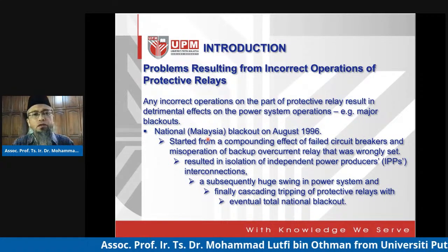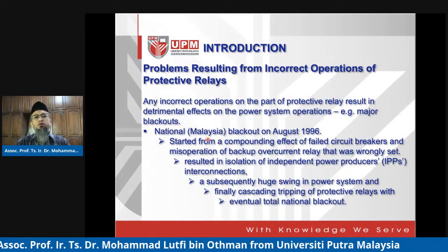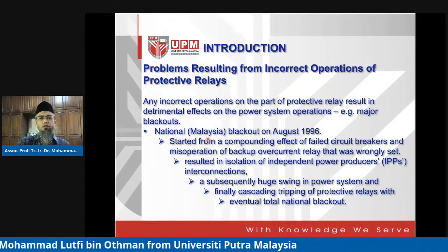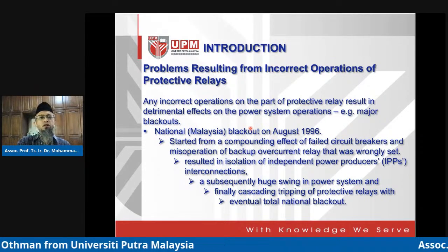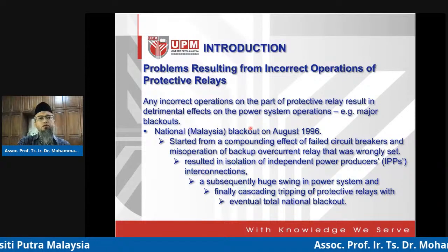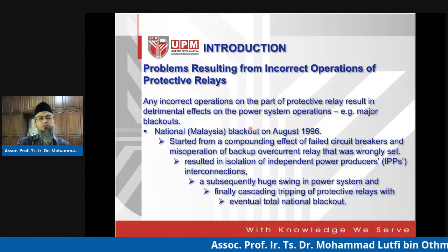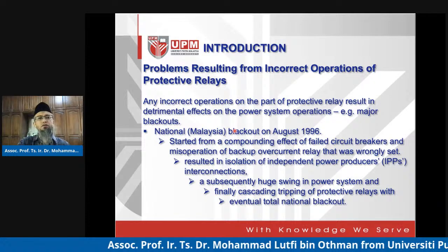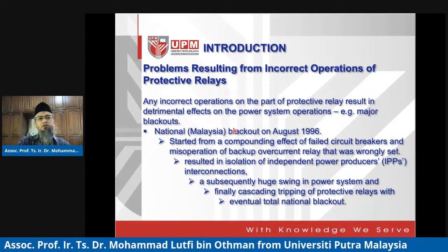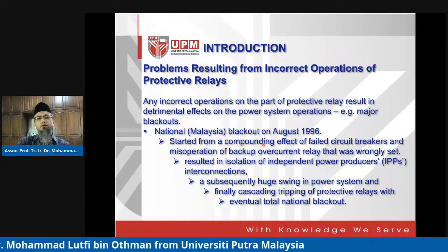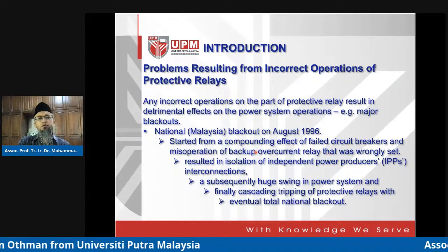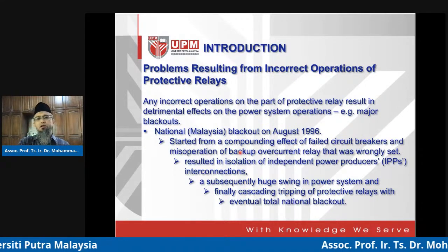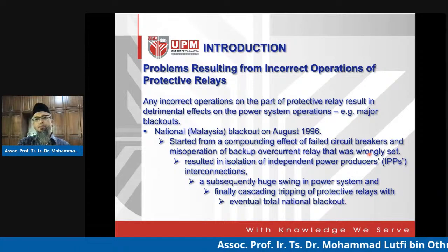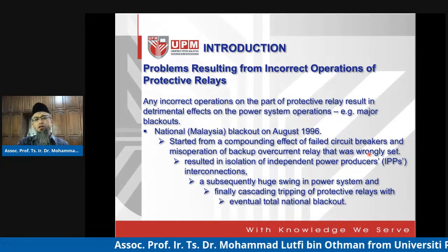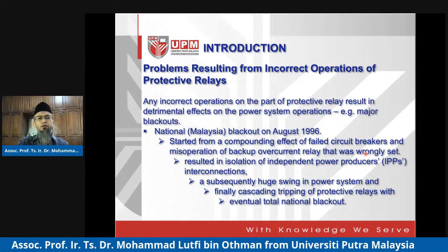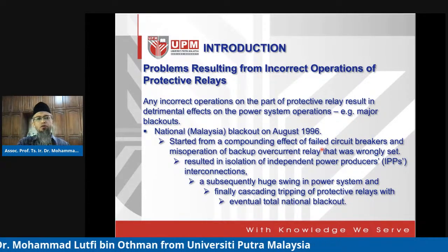A case in point: because of the incorrect operation of a protective relay, there was one major blackout that occurred back in 1996. It was a very bad national blackout that occurred in Malaysia. It basically started off seemingly quite trivial, from a compounding effect of failed circuit breakers and simply a misoperation of some backup overcurrent relay that was wrongly set. So you can see the issue here is a wrong setting of the overcurrent relay. But this basically resulted in a major problem.